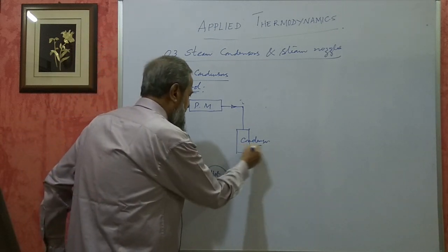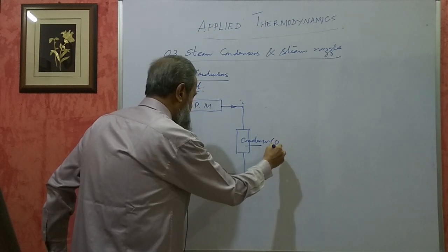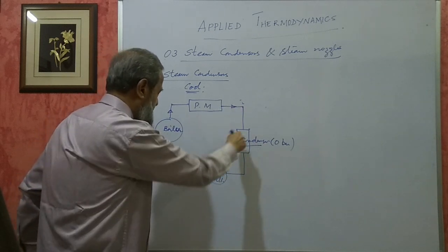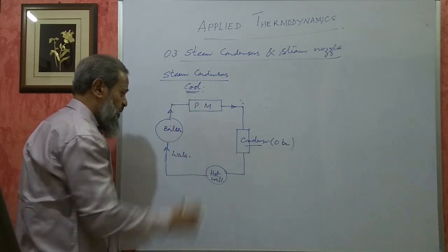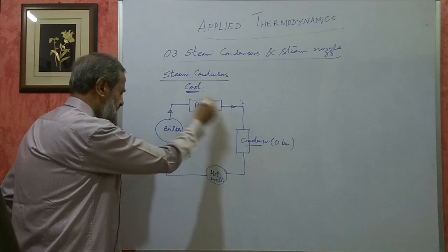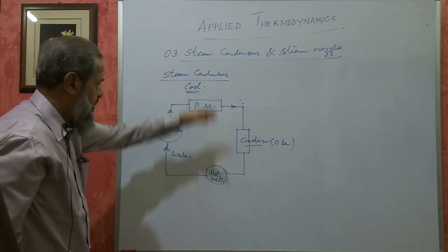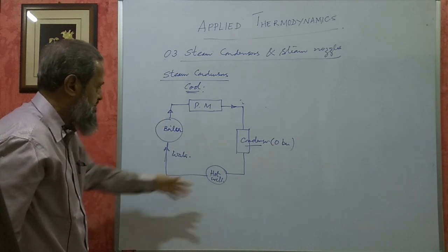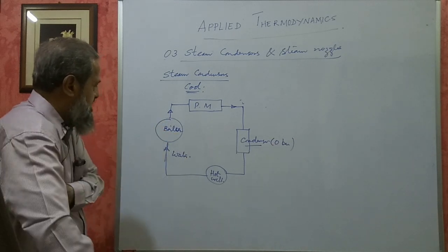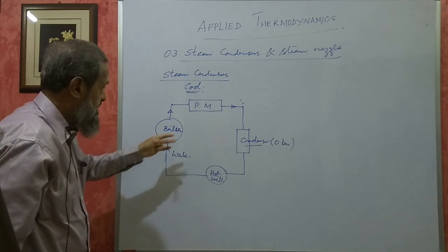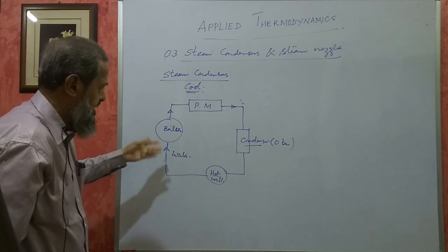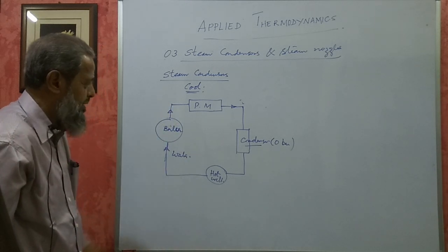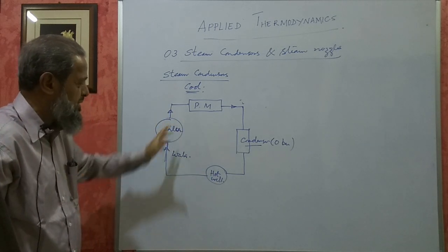Because the condenser is almost at 0 bar absolute pressure, very close to 0, you can discharge the steam into it at a very low pressure - that means you can get more work. That is one of the advantages. The overall efficiency of the plant will increase. The boiler will not get corroded since the same water is being used. Corrosion will be less and there will be no need for a feed water treatment plant. The same water keeps getting circulated.